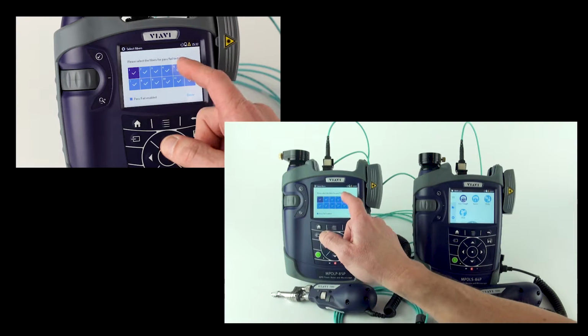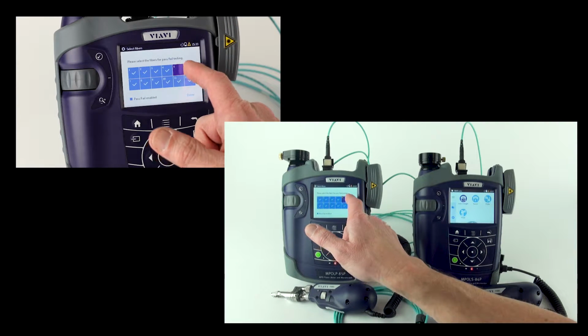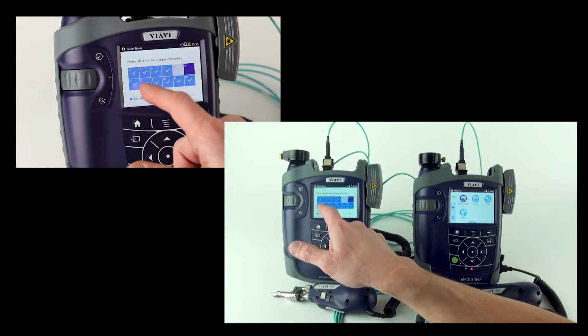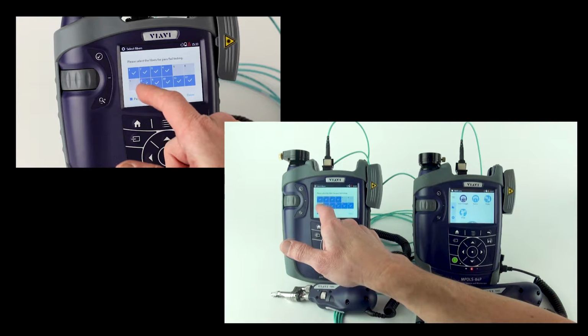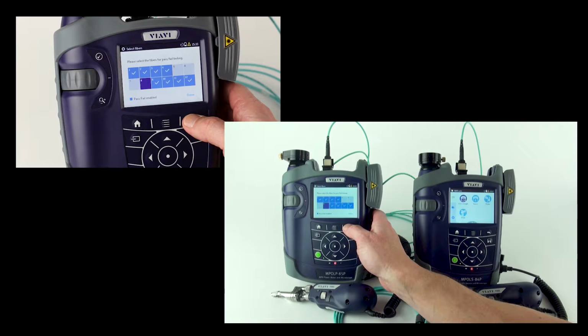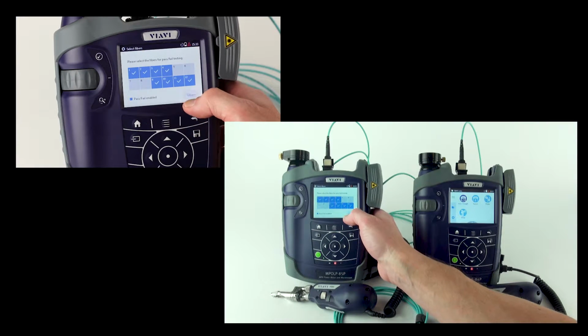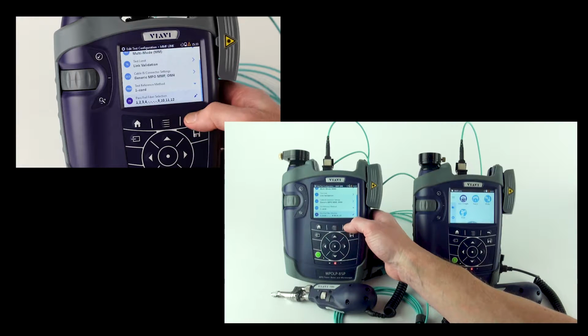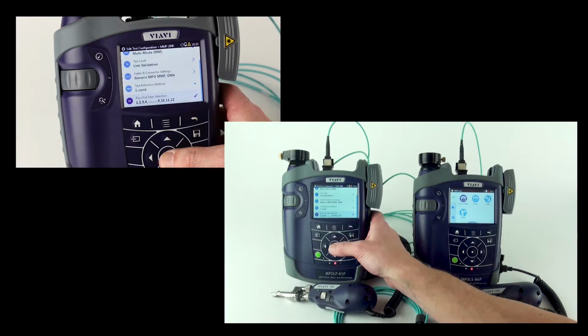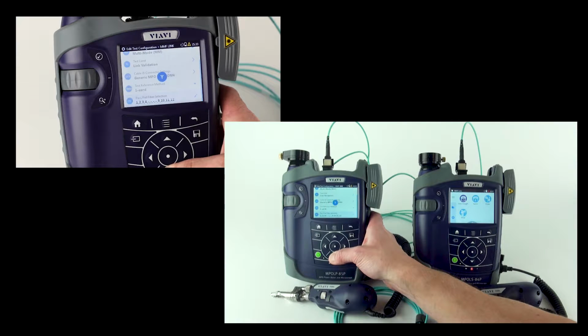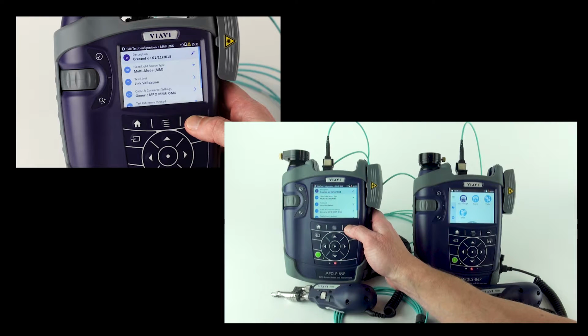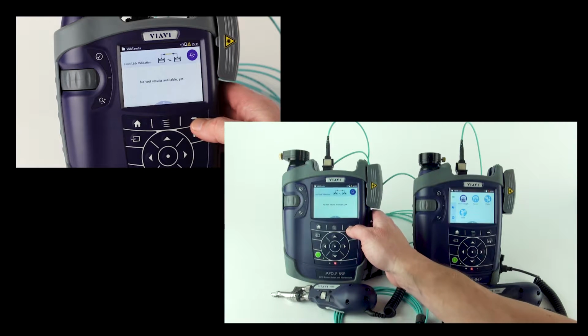All fibers are tested, but in a lot of cases, certainly for your SR4 technology, your middle 4 fibers are not used, and so you may want to disable them. It doesn't mean that they don't get measured, it just means that they don't count to the pass-fail analysis. So even if they have excessive loss, you won't fail due to them. And for setting up a test, that's really all there is to it. It's very simple, very straightforward.